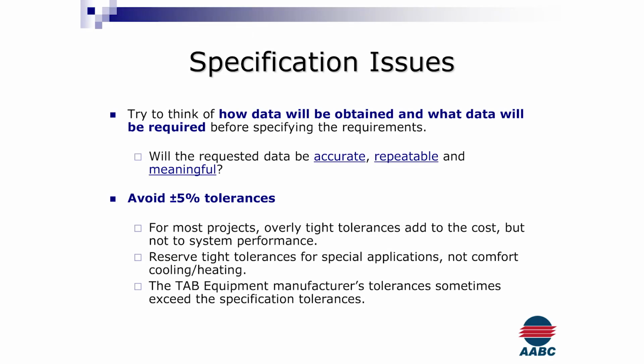It's really important that when we get to a job there are no gray notes at the top of the drawing saying you will rebalance the entire system—this could be a 9-floor air handling unit where we're only touching one soiled utility suite and a corridor off of it. So it's very important to get a clear, specific definition of what systems we're actually going to work on, as well as tolerances. One of the other hang-ups is that nowadays it's very popular to have a 5% plus or minus tolerance.